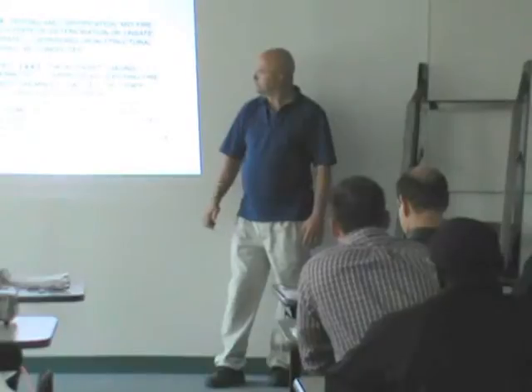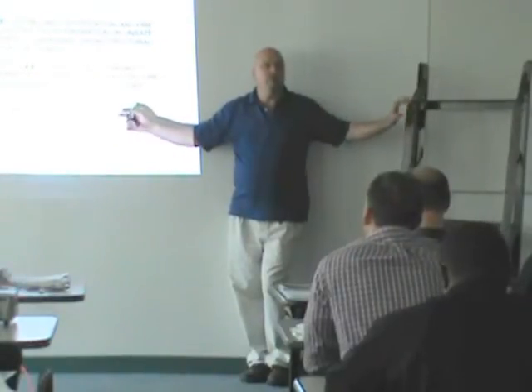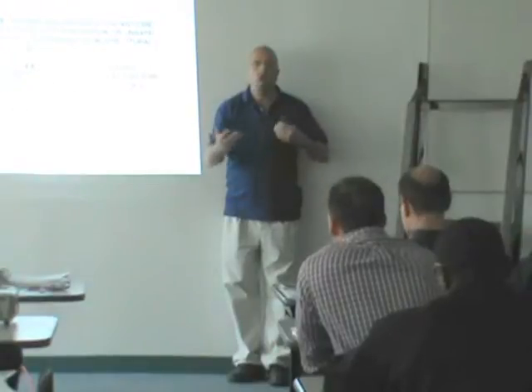The NFPA says: the authority having jurisdiction shall be permitted to approve any existing fire escape that has been shown by load test or other evidence of strength. Now five years later, if the fire escape has been maintained and all the connections are still good, can your engineer give you other evidence of strength for another five years? The average life of a refurbished fire escape is 15 to 25 years — because in 25 years, the bolts should be swapped out again. The authority having jurisdiction decides. If you fully refurbish it instead of load testing, you get certification. In case of financial problems, what are some options?